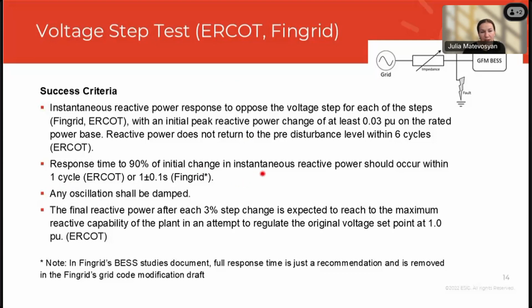Any oscillation shall be damped, and then final reactive power after each 3% step is expected to reach maximum reactive capability in the effort to regulate voltage in the POI to 1 per unit. That's what ERCOT defines.